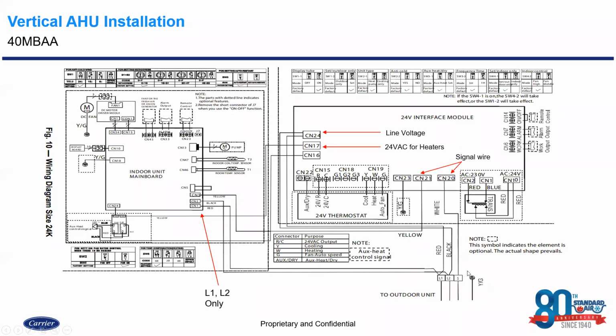So let's start at the bottom here. You can see your bus bar, your main power coming in. Essentially, all that we're doing is we're wiring up just like any ductless indoor unit. We're wiring up L1, L2, and S. Everything beyond the top of this bus bar going in is already factory wired.